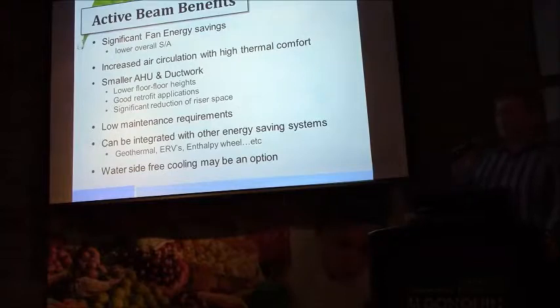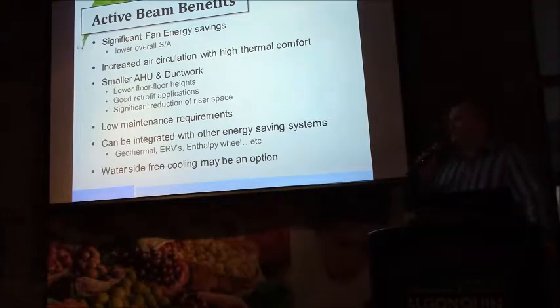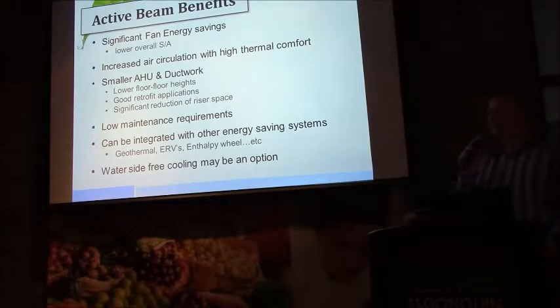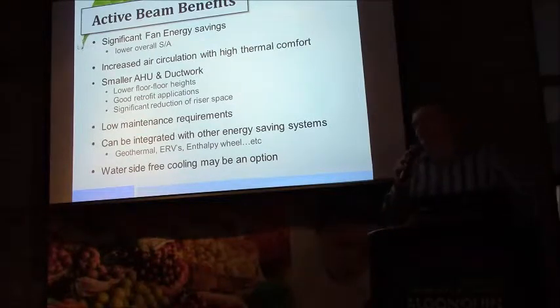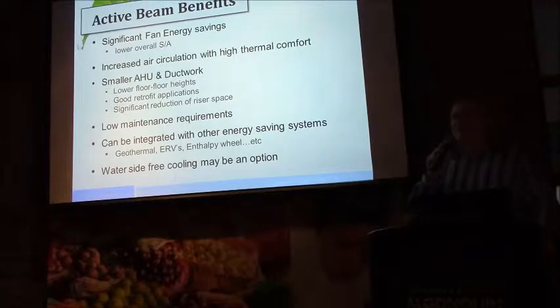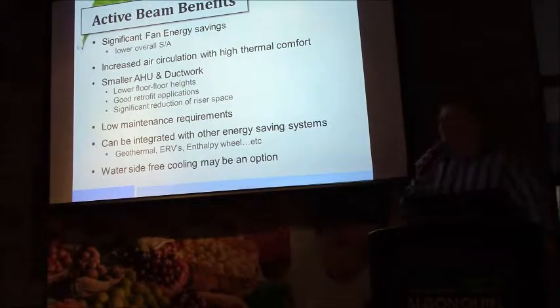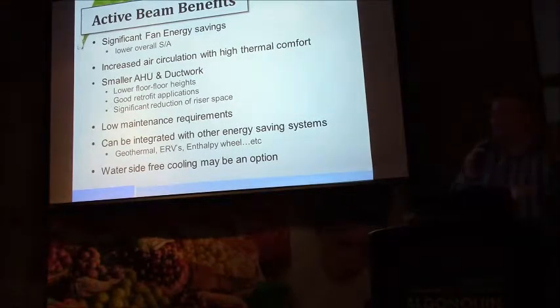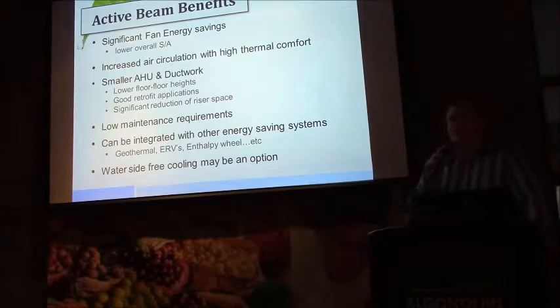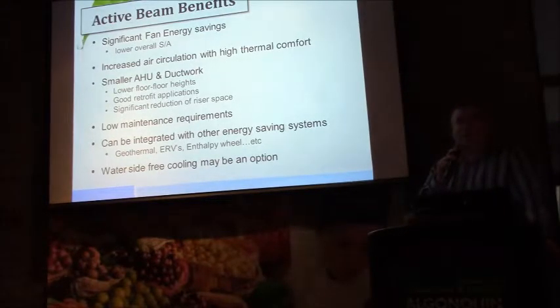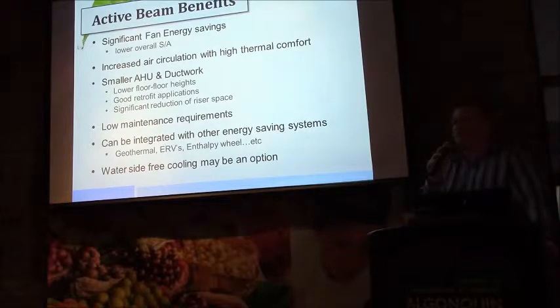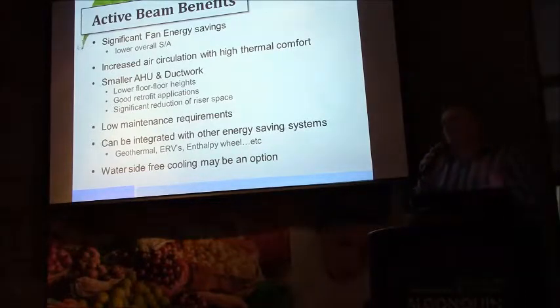So to recap, the active beams as a decoupled ventilation system are lowering our overall fan energy. We have the benefit of smaller ductwork, although I oftentimes encourage consultants to consider upsizing that ductwork slightly. And the reason for that is churn in the space effectively. If we agree that we've cut the air handling system in half when compared to an all-air system, sizing the air handling unit for something, say, at 400 feet per minute instead of 500 feet per minute intrinsically builds in an opportunity for scalability to the design.